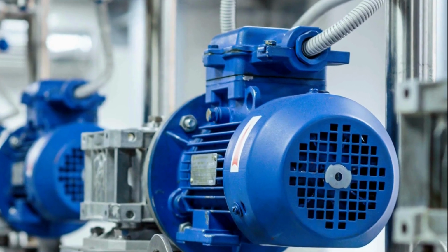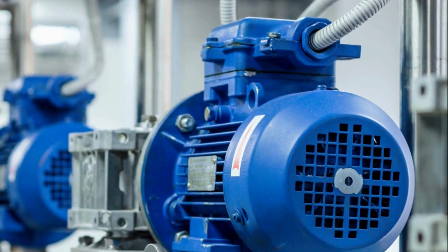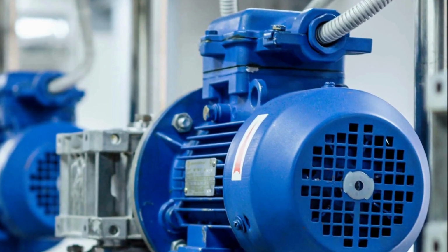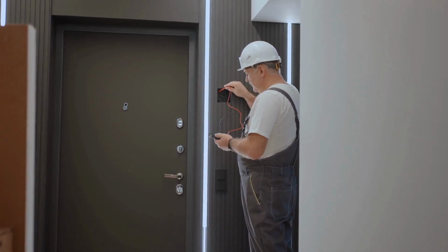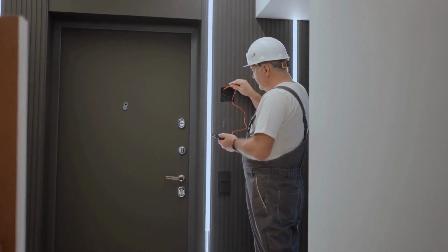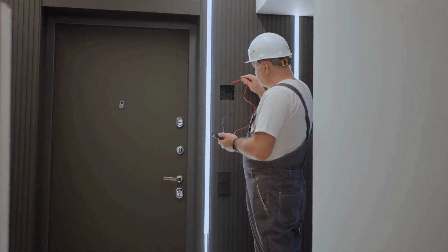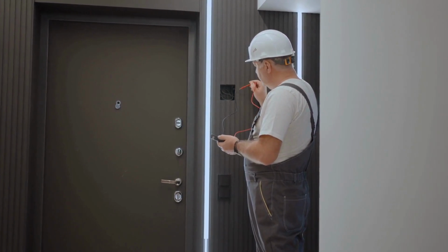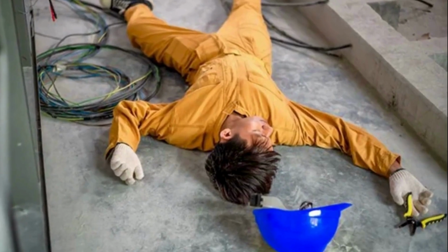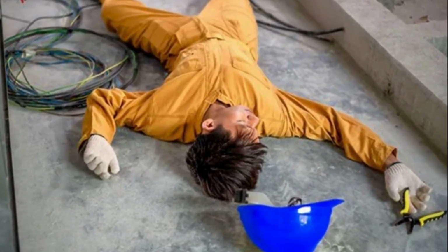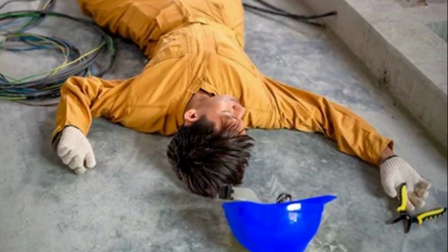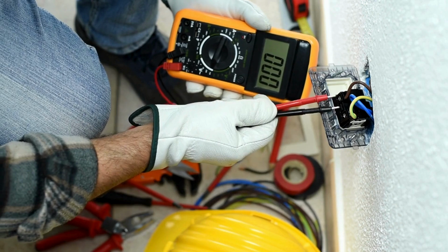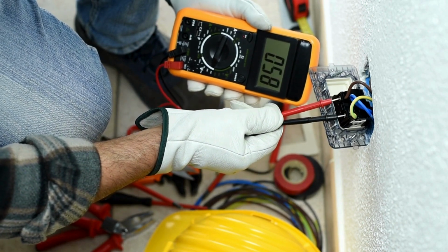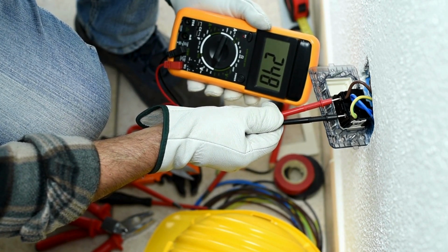Think about this for a second. You could have a motor drive that's been sitting unpowered for 10 minutes. Your voltage tester says it's dead, but inside that drive, capacitors are holding hundreds of volts, sometimes even after an hour or more. The moment you touch the wrong terminals, that stored energy dumps through you faster than you can pull your hand back. This isn't a theoretical problem. This happens to experienced electricians who do everything else right.